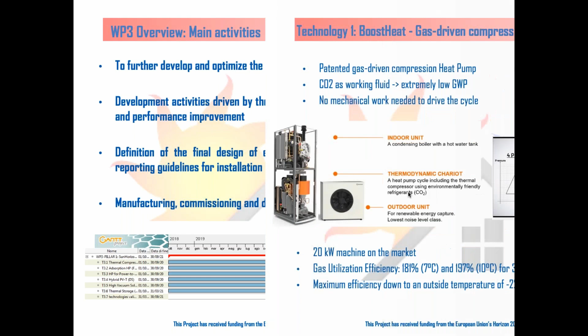Starting from the first technology in SunHorizon: this is an example of a technology already on the market but at a very early stage, the BoostHeat gas-driven compression heat pump. It is not like a standard gas-driven sorption heat pump, which is more established on the market. This is a real compression cycle working with CO2 as the working fluid, so extremely low GWP, basically a GWP of 1. But the main innovation is that in this case we are not providing any mechanical work from electricity to run the compression cycle.